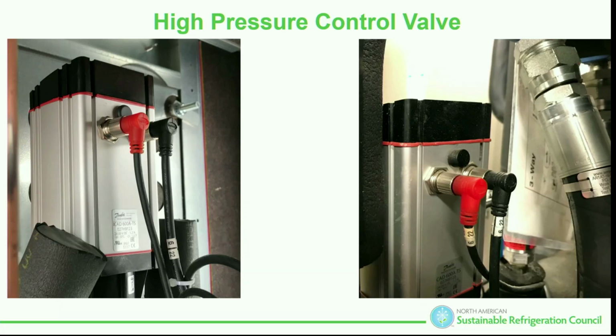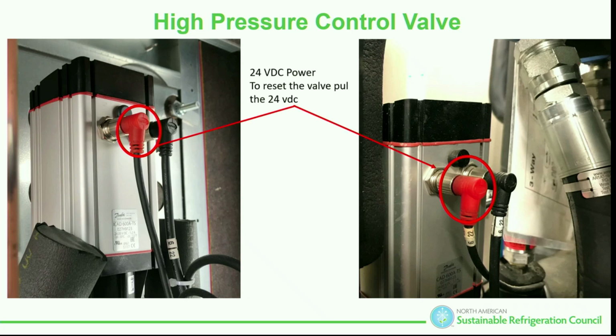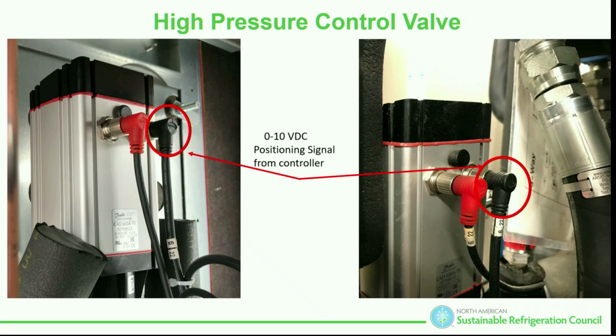I've got 24 volt power. I got a 0 to 10 volt signal. I got one of these that somebody murdered. Yes, they murdered it. They put thermal paste on it and destroyed it. But what we did is, I don't know how they did it, but we were getting 0 to 10 volts off of the controller, but we were not seeing anything here.